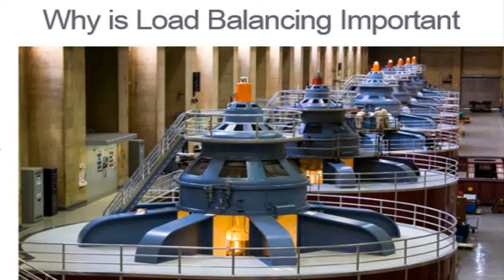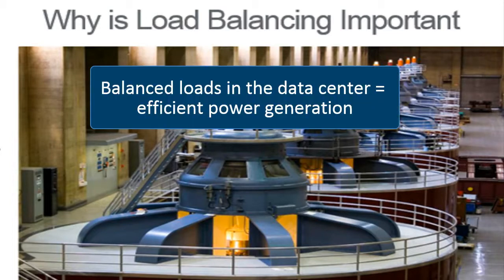A little background. You might know the term load balancing goes back to the mechanical generator — a heavy piece of rotating machinery riding on bearings. It's obvious that the mechanical loading on these bearings must be balanced, because unbalanced loads accelerate wear and result in inefficient power generation. Drawing unequal amounts of power from a three-phase generator creates a mechanically unbalanced system. Running unbalanced loads in the data center results in excess heat in the power cables and unwanted harmonics. In addition, you may get a fine from the utility company if you aren't drawing equally from the three phases.